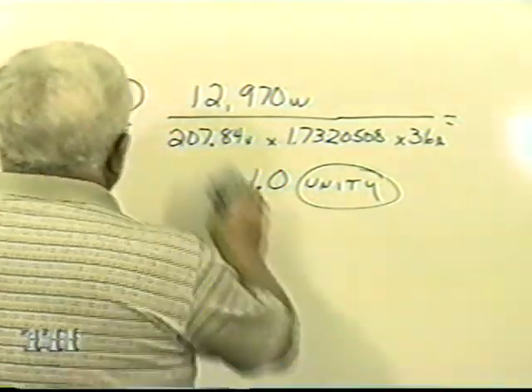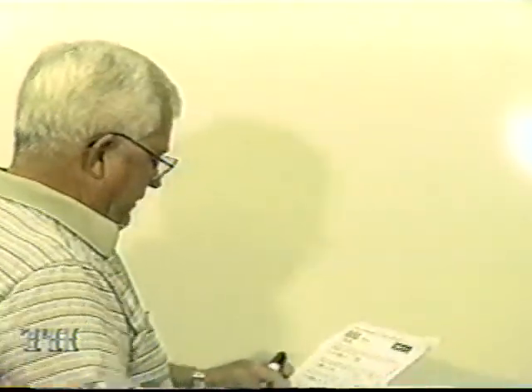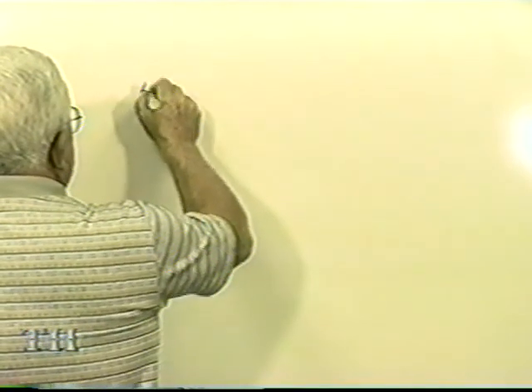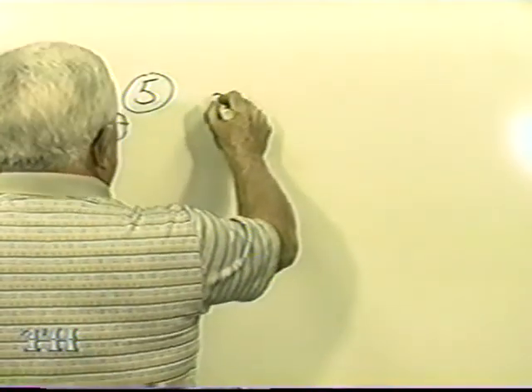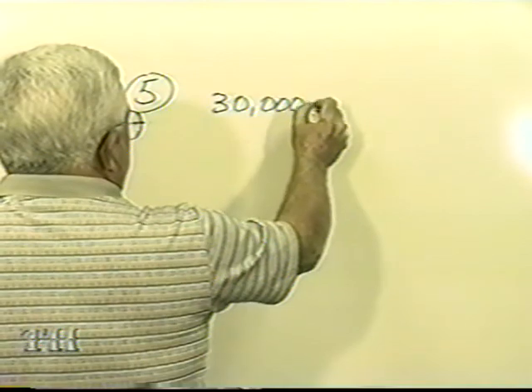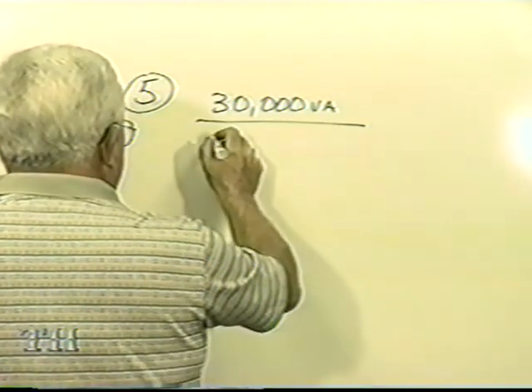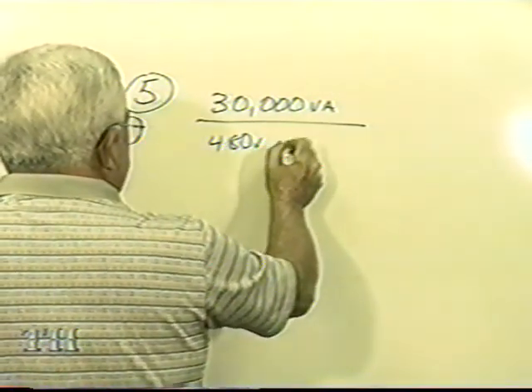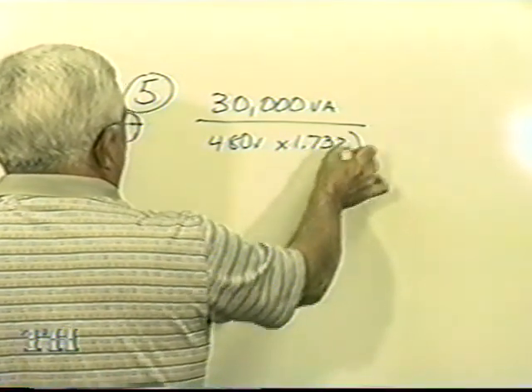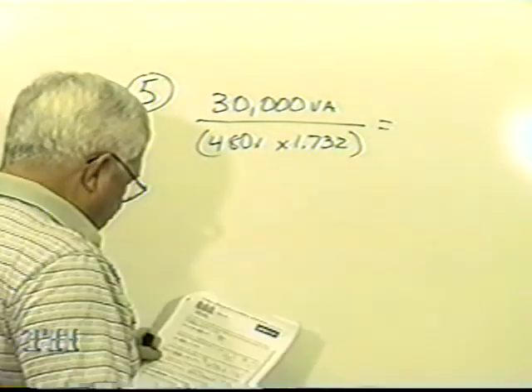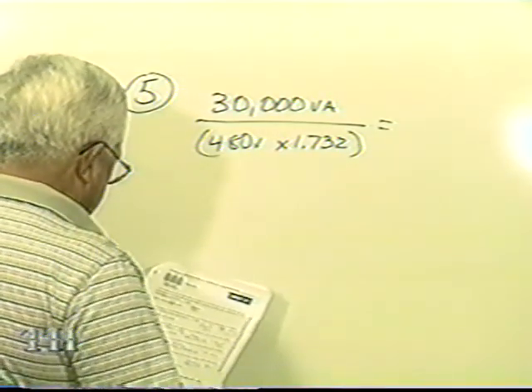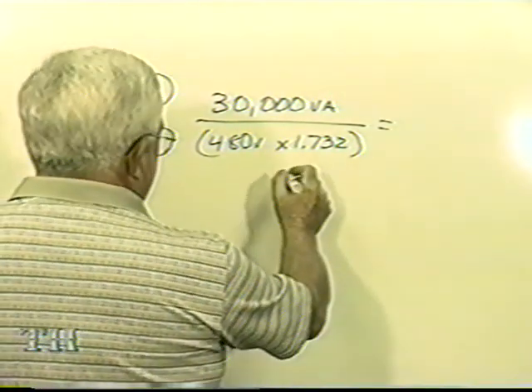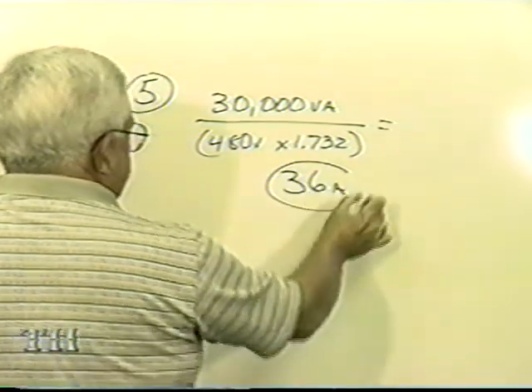Number 5. We've got 3 10 kVA single phase transformers. If I had 3 10 kVA, that'd be a total of 30. And if I divide that by 480 volts at the square root of 3, run that in your calculator with 2 bottom line dividers, what is the primary line current? 36 amps.